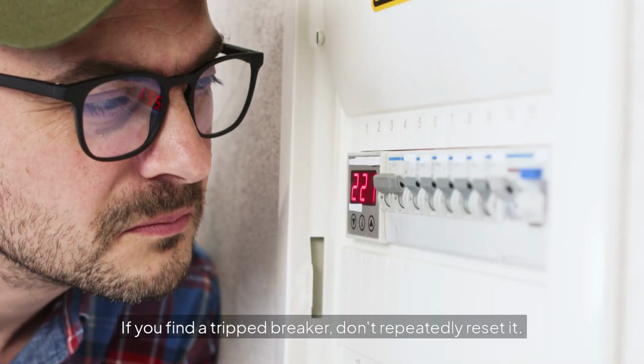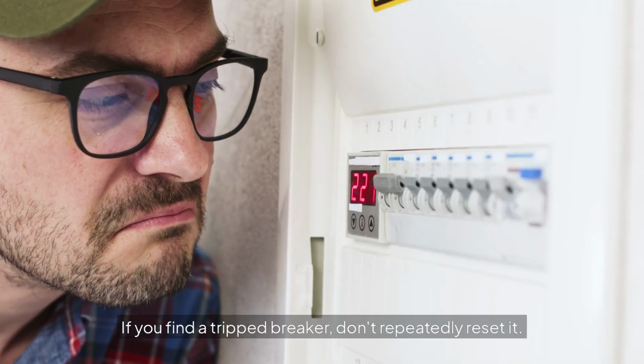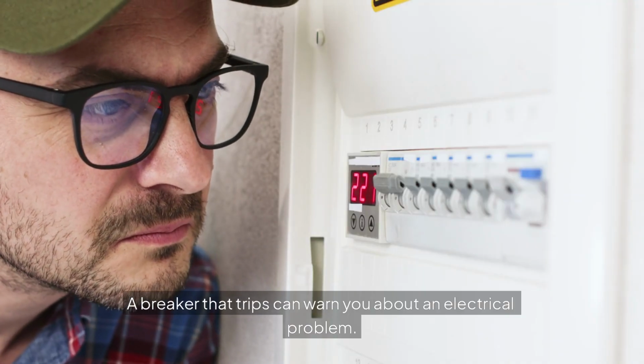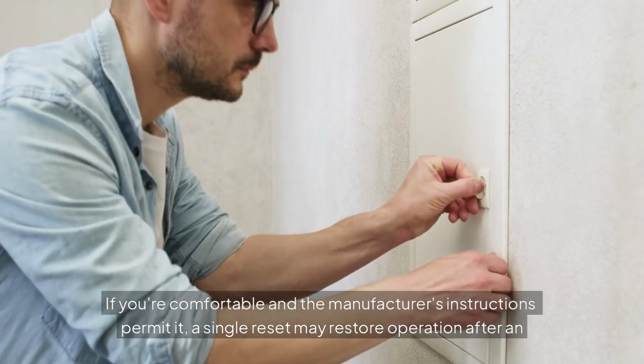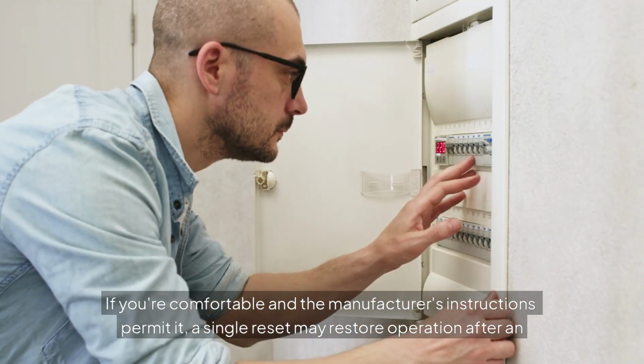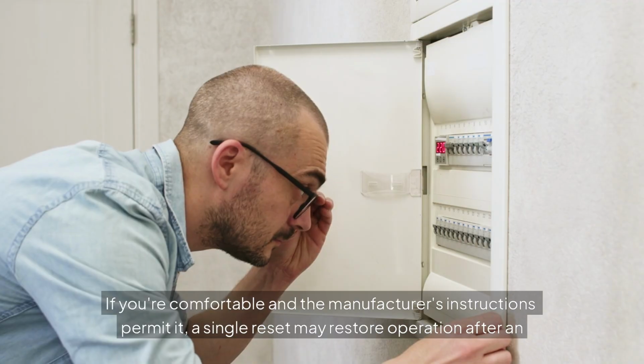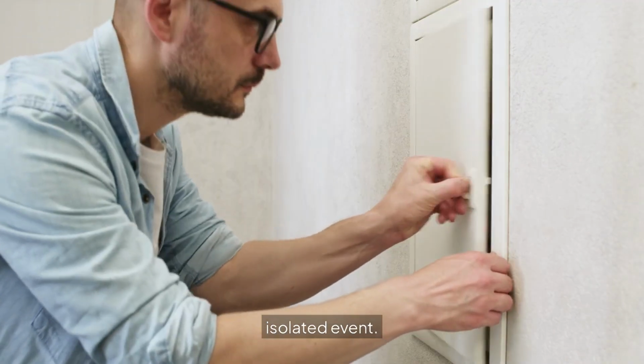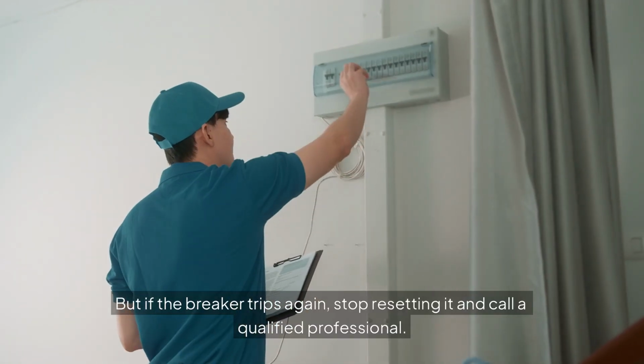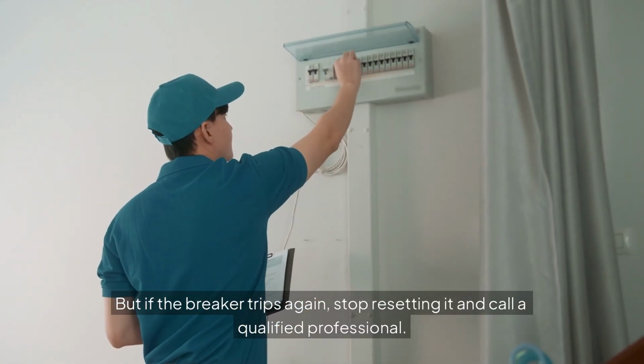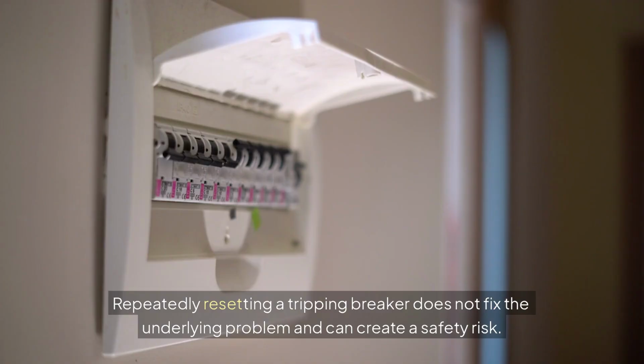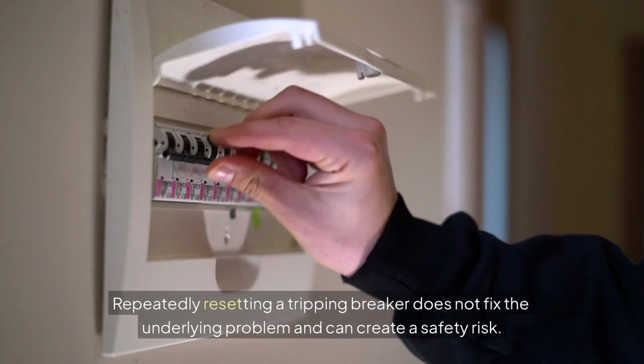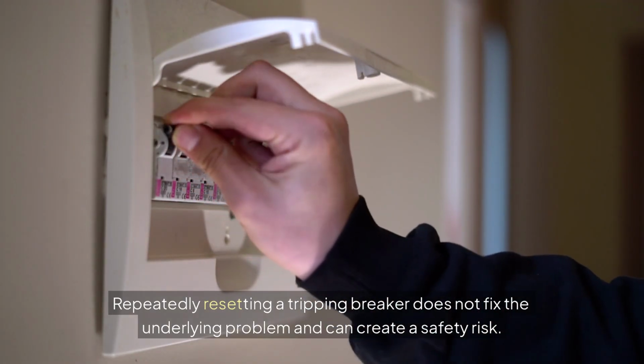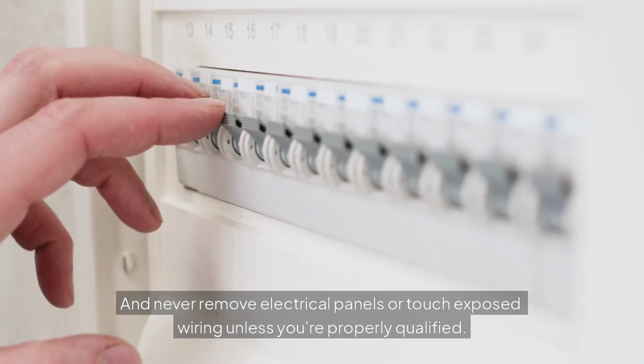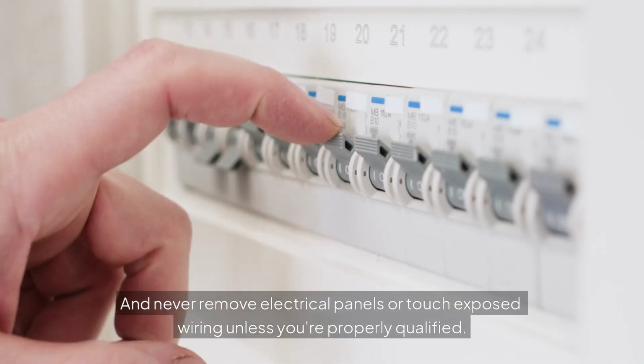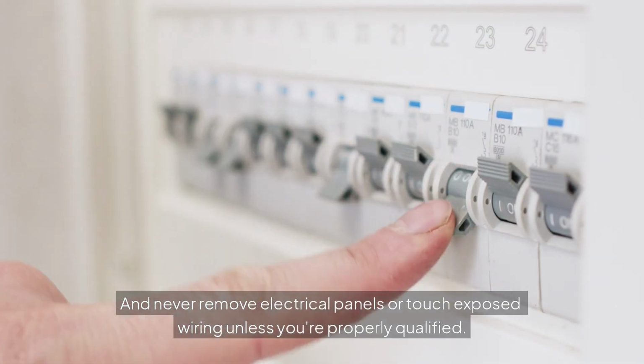If you find a tripped breaker, don't repeatedly reset it. A breaker that trips can warn you about an electrical problem. If you're comfortable and the manufacturer's instructions permit it, a single reset may restore operation after an isolated event. But if the breaker trips again, stop resetting it and call a qualified professional. Repeatedly resetting a tripping breaker does not fix the underlying problem and can create a safety risk. And never remove electrical panels or touch exposed wiring unless you're properly qualified.